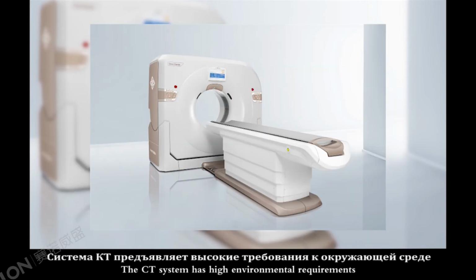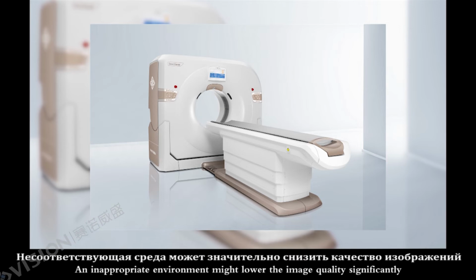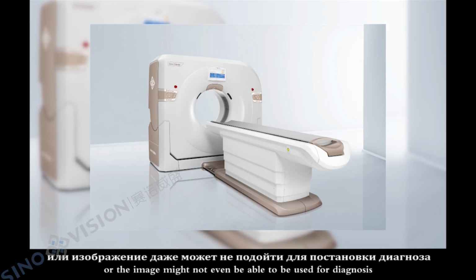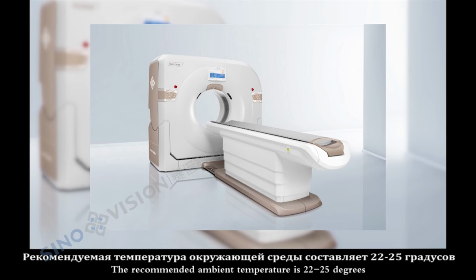The CT system has high environmental requirements. An inappropriate environment might lower the image quality significantly, or the image might not even be able to be used for diagnosis. The recommended ambient temperature is 22 to 25 degrees, and the optimum humidity should be maintained between 40 to 60%.